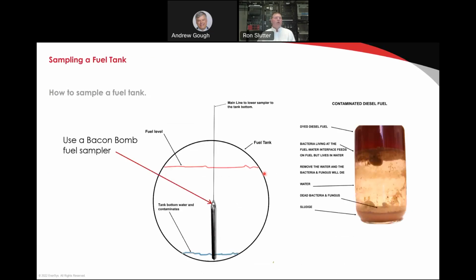All right, so now let's talk about diesel fuel for your generator. What we have here is a picture of the internal portion of a tank, and the red line represents the top of the fuel, the blue representing the area that can contain contaminants. Looking at the glass on the right-hand side, we have an area of water. It doesn't look good. This is pretty typical in fuel tanks that are not taken care of well. We have contaminated diesel fuel in the bottom of the tank.